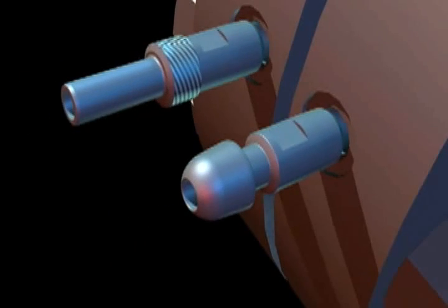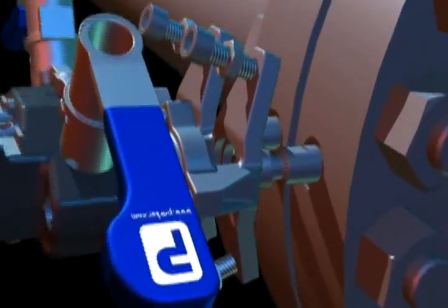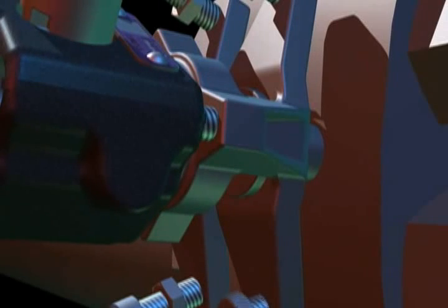The system features an integrated mounting and manifold lock that connects differential pressure transmitters directly to process piping. Direct mounting replaces typically handcrafted assemblies of discrete tubing, joint and valve components that can take several man days to fabricate. There are two interlocking elements to this mounting solution.